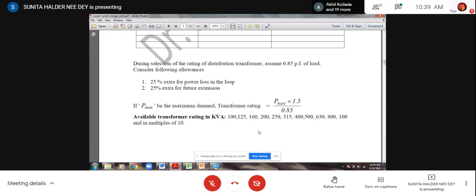Since your transformer rating has come to 1350, you cannot take 1250. Why 1250? Its available rating is 125 or multiples of 10, so 125 is available as well as 1250. But your requirement is 1350, so it cannot meet that. So you have to go for the next rating. All of you have got my point?